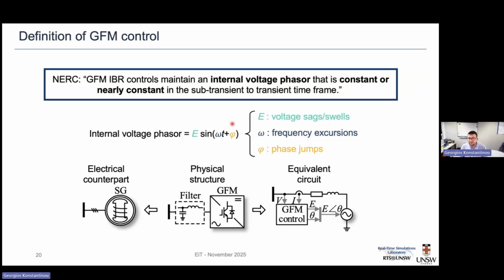Finally, and the point that seems most interesting in recent analysis, there's phi. How do we maintain this constant phasor, and what happens to the phasor generated by a power electronics converter when there's a change in angle? How does the converter respond during phase jumps? So we see that all the events we expect in the network effectively translate into one of these three cases, or combinations of them, for our converters — voltage dropping or increasing, frequency dropping or increasing, phase jumping forward or backward, changing this network value.